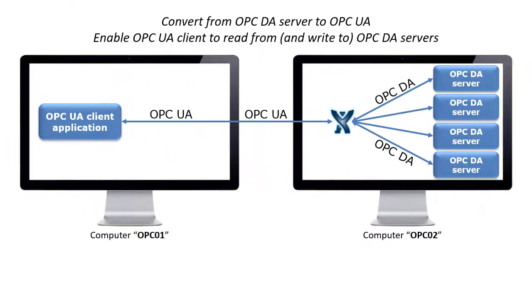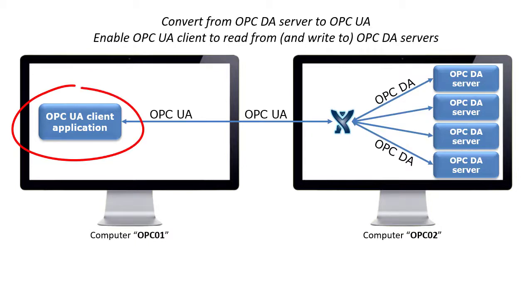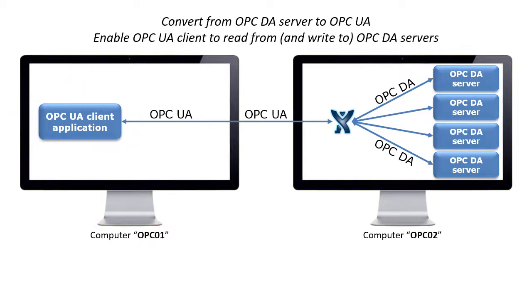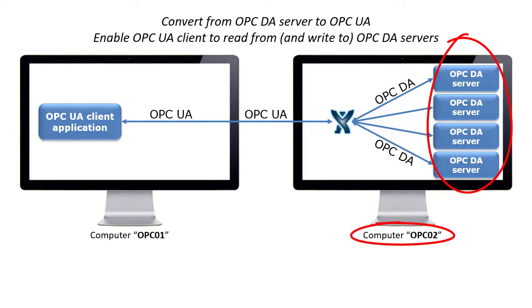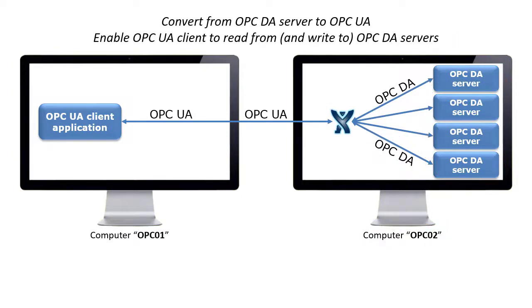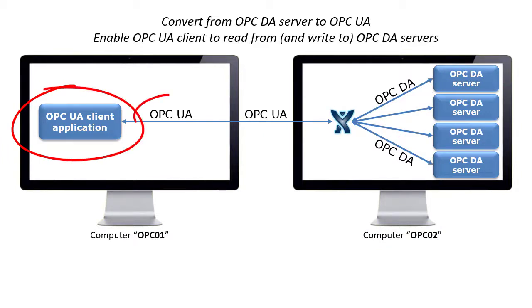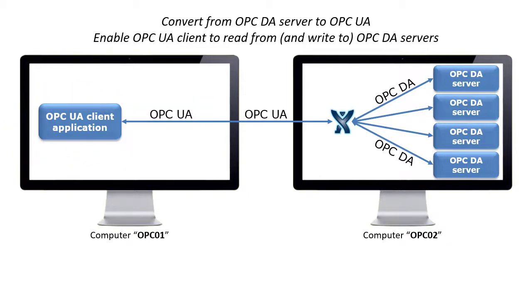In this example, we use Unified Automation on computer OPC 01. We have four servers on computer OPC 02, which only support OPC DA. Unified Automation only supports OPC UA. It cannot connect directly to an OPC DA server, so we need to use OPC Expert as a converter.